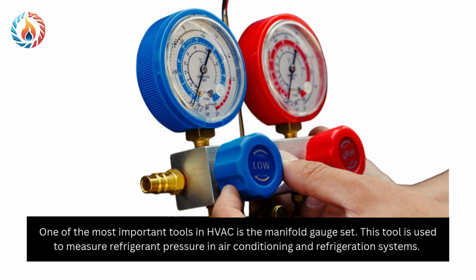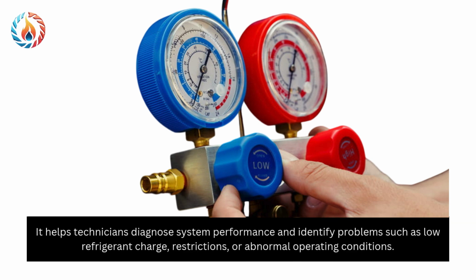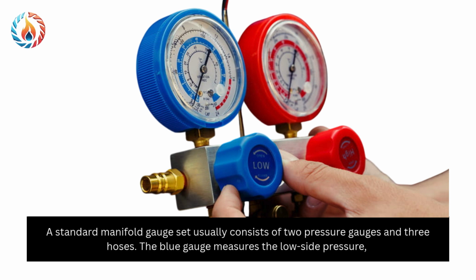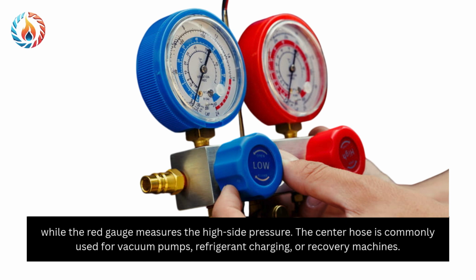Manifold gauge set. One of the most important tools in HVAC is the manifold gauge set. This tool is used to measure refrigerant pressure in air conditioning and refrigeration systems. It helps technicians diagnose system performance and identify problems such as low refrigerant charge, restrictions, or abnormal operating conditions. A standard manifold gauge set usually consists of 2 pressure gauges and 3 hoses. The blue gauge measures the low side pressure, while the red gauge measures the high side pressure. The center hose is commonly used for vacuum pumps, refrigerant charging, or recovery machines.